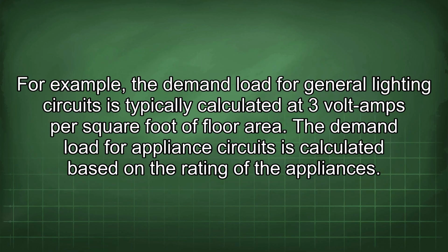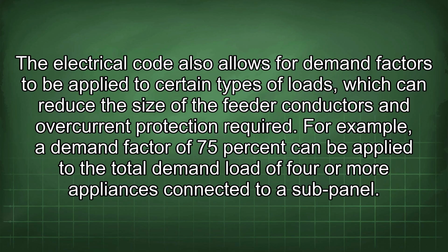For example, the demand load for general lighting circuits is typically calculated at 3 volt-amps per square foot of floor area. The demand load for appliance circuits is calculated based on the rating of the appliances. The electrical code also allows for demand factors to be applied to certain types of loads, which can reduce the size of the feeder conductors and overcurrent protection required.